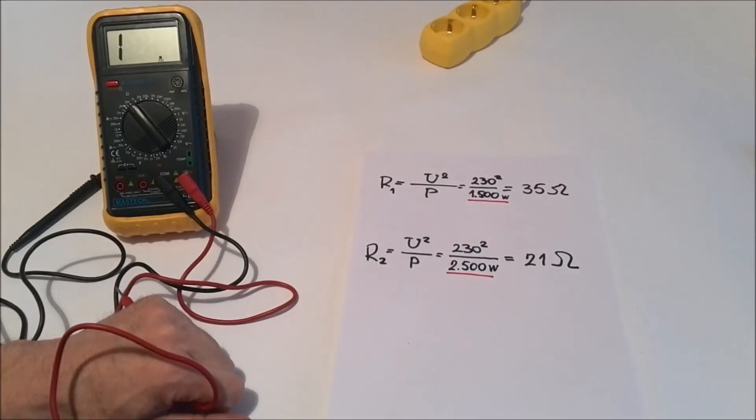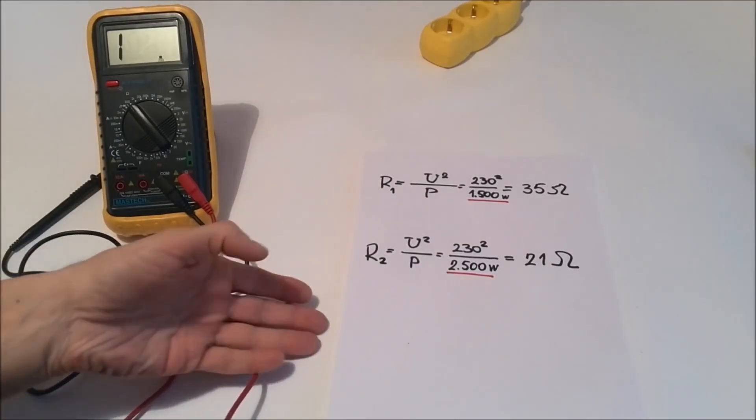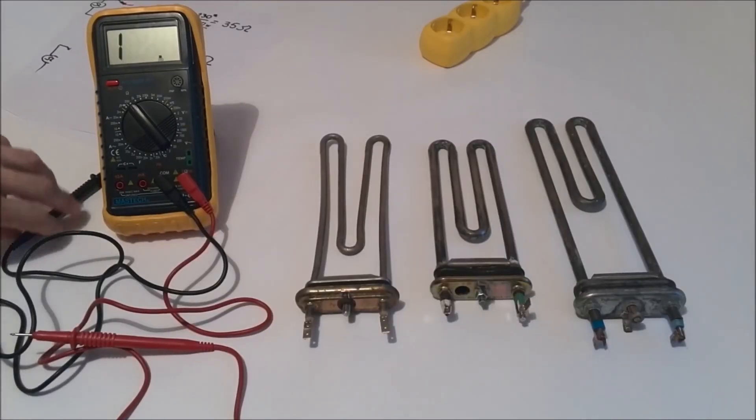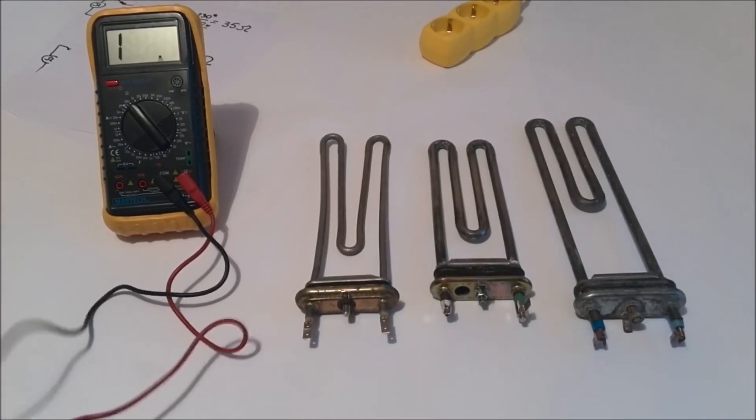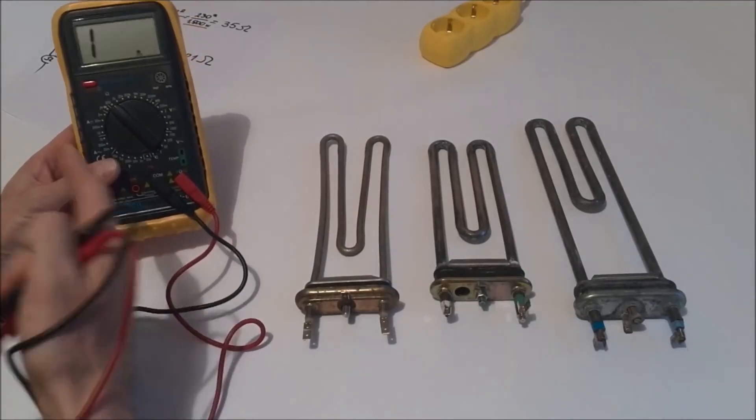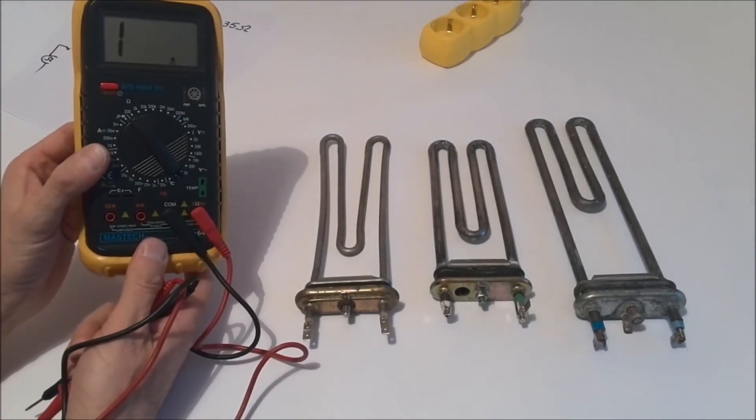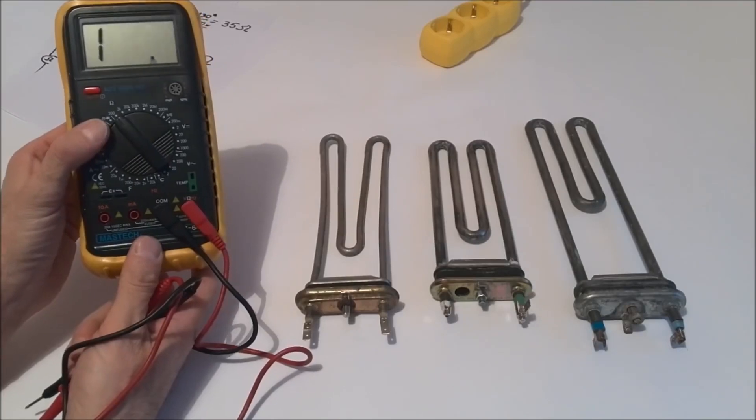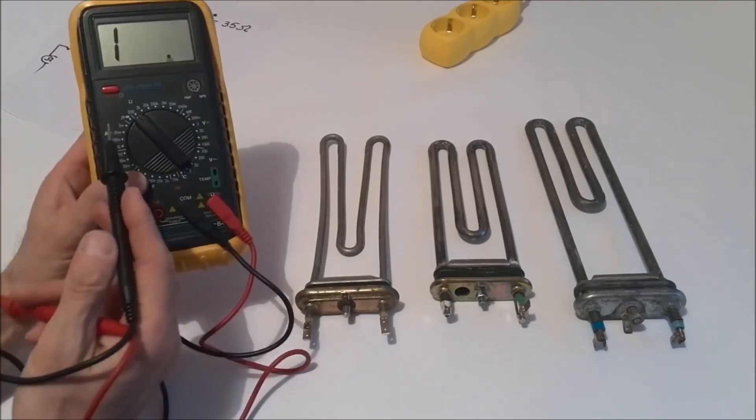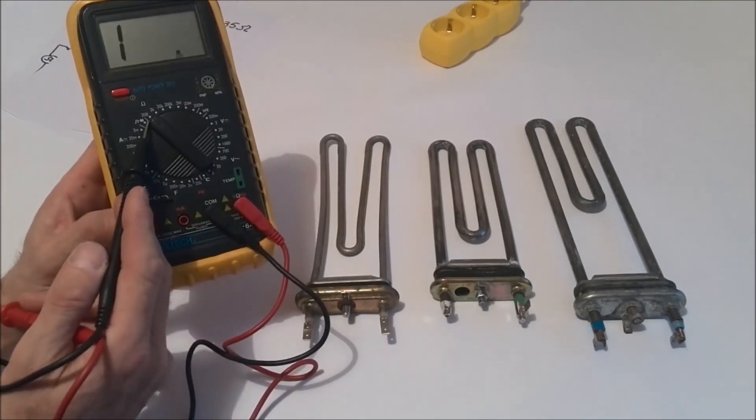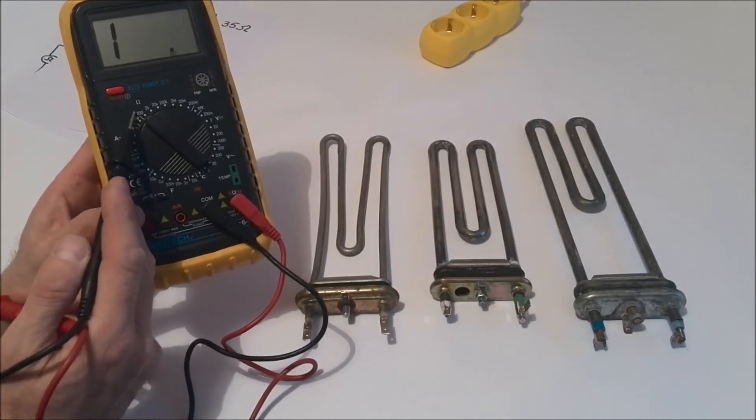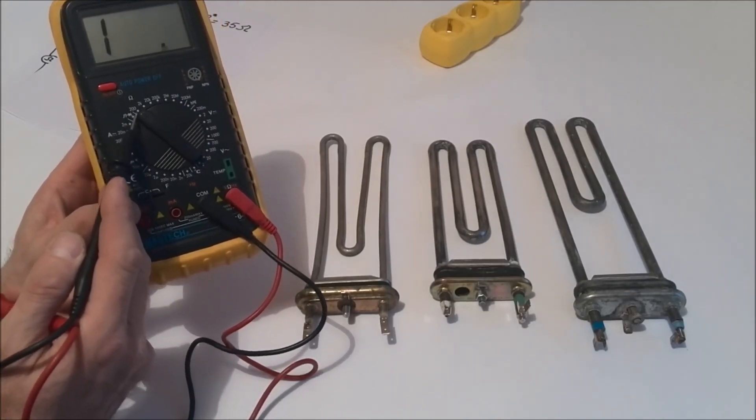We will now practically show how we test the functionality of the pipe heaters. Here we have three heaters whose functionality we need to determine. We have seen from this calculation that the resistance of the heaters is somewhere in the range of about 15 ohms to about 40 ohms. So we will take our multimeter and adjust to measure the resistance and a range of 200 ohms is enough for us.